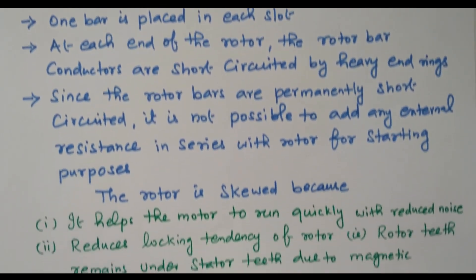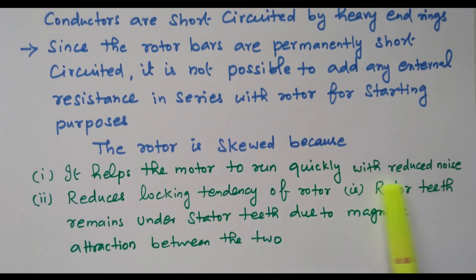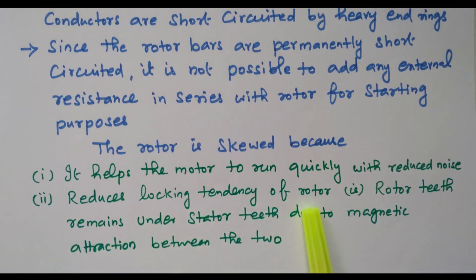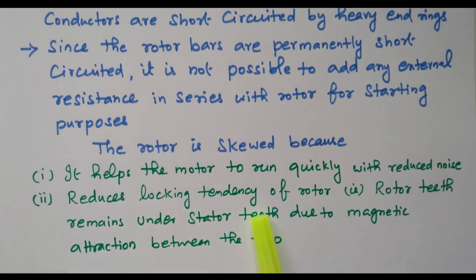The rotor is skewed — not a straight line — for two main reasons. First, it helps the motor to run quietly with reduced noise. Second, it reduces the locking tendency of the rotor. If the conductors were placed in a straight line, there would be a possibility of locking between the stator and rotor teeth due to magnetic attraction. Skewing introduces a phase difference between stator and rotor, thus avoiding this locking tendency.